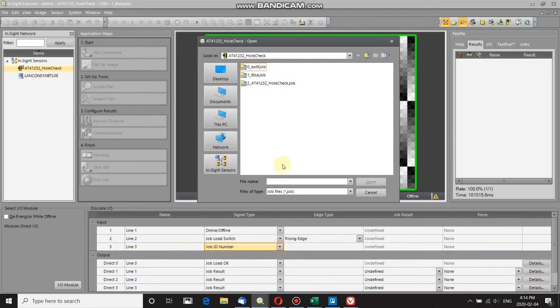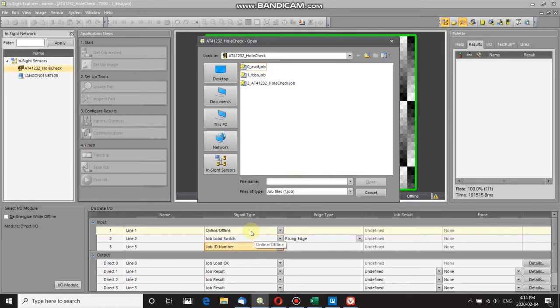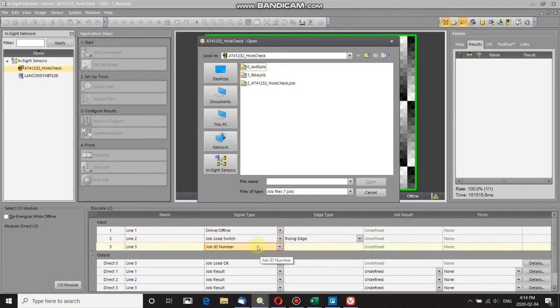To change a job, what I first need to do is turn the camera offline, and I'm doing that here with an online/offline signal. Then you need to set your job ID number lines high or low to the number corresponding to the job you want to load.